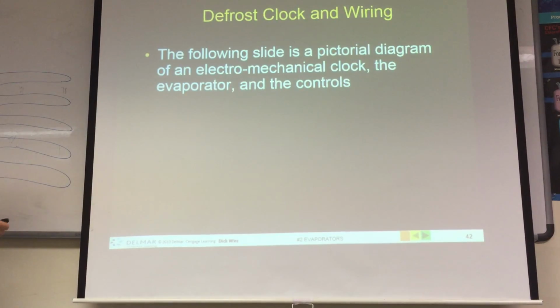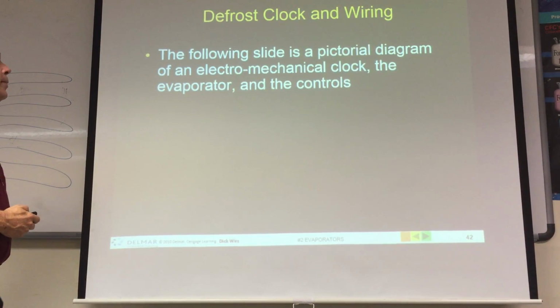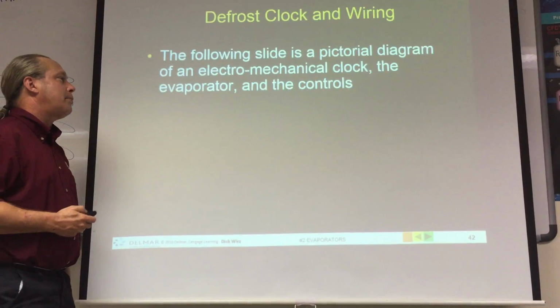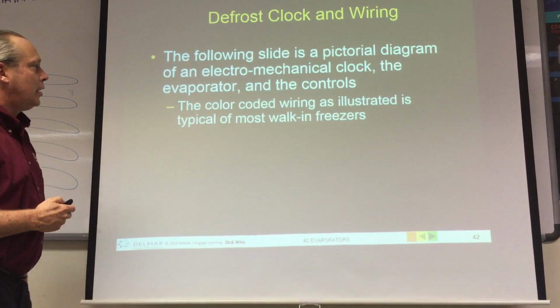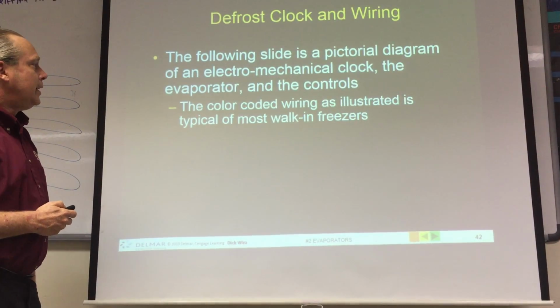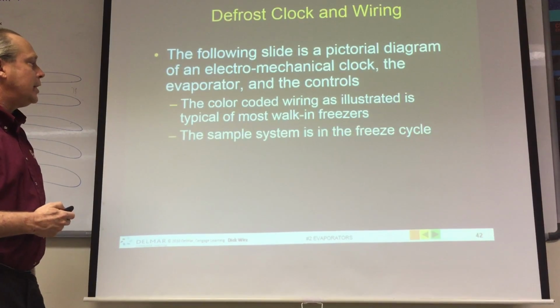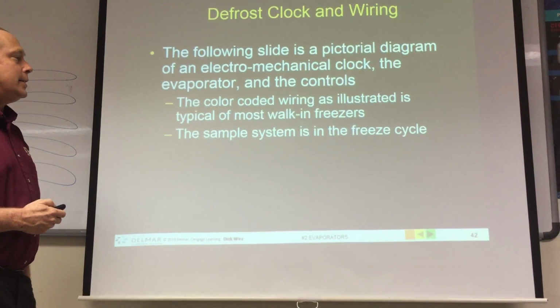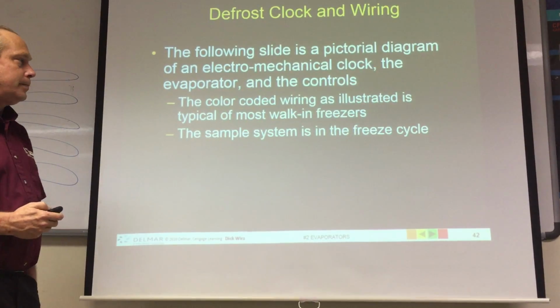Defrost clock and wiring. The following slide is a pictorial diagram of the electromechanical clock, the evaporator, and the controls. The color-coded wiring illustrated is typical of most walk-in freezers. The sample system is in the freeze cycle.